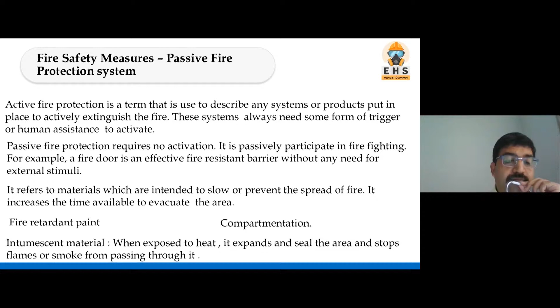Compartmentation, I already told you, uses some intumescent material. Earlier we discussed the spread of fire in the shaft—this shaft should be sealed using an intumescent material which, when exposed to heat, expands and seals the area, stopping flame and smoke from passing through. So whatever is not actively participating, but is involved in avoiding the spread of fire, is called the passive fire protection system.